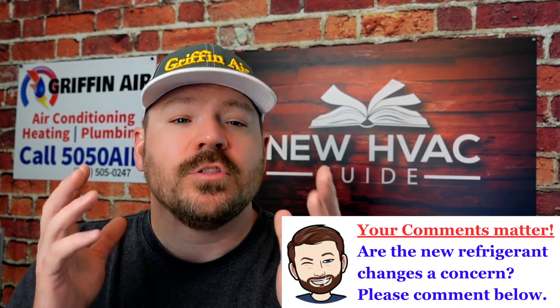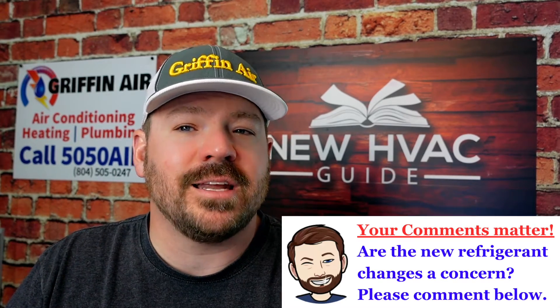If you're watching this video and thinking about adding anything to that system — refrigerant, oils or lubricants, leak seal — anything the manufacturer has not approved could void your warranty. Also, although the pressures are very similar with R32, the discharge temperature is significantly higher. This will increase the wear and tear on things like the compressor. If it's not intended to use that much heat and the compressor is getting hotter than originally intended, you can have significant breakdowns just because you switched the refrigerant.